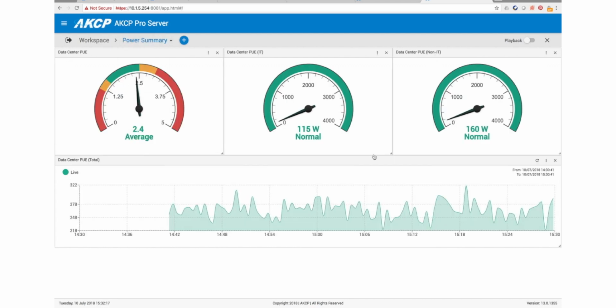And using our virtual sensors, we're calculating live PUE readings. So you can see here, this is our total data center power load over the past hour. And then here we have our non-IT load, and here we have our IT load. And then over here we're calculating the PUE based on those two numbers.